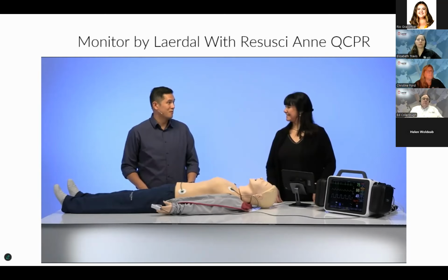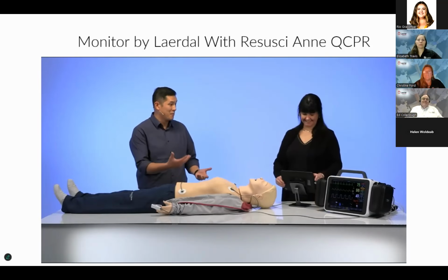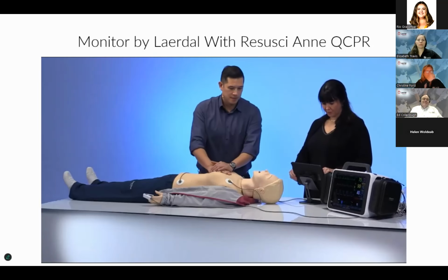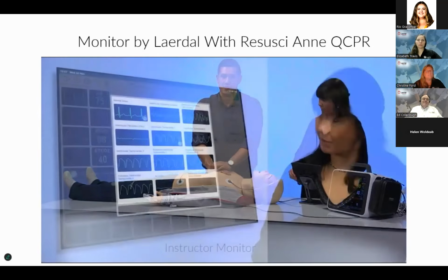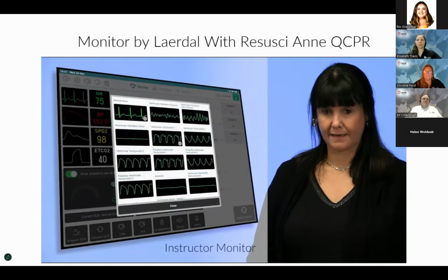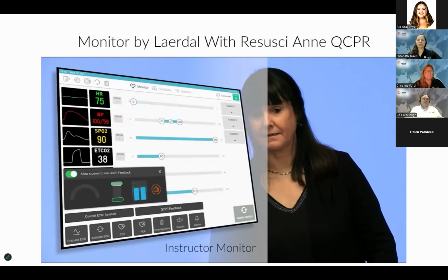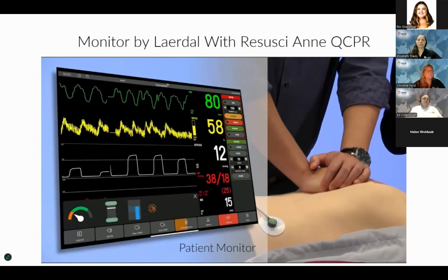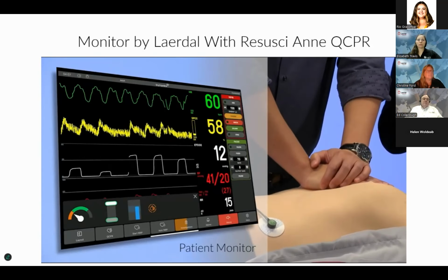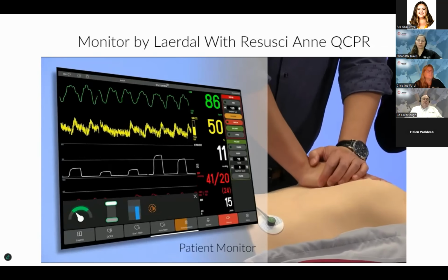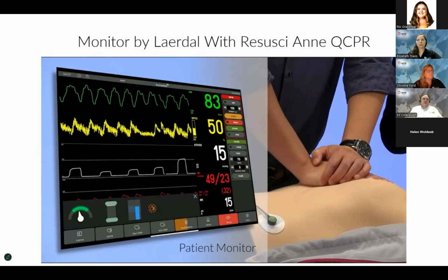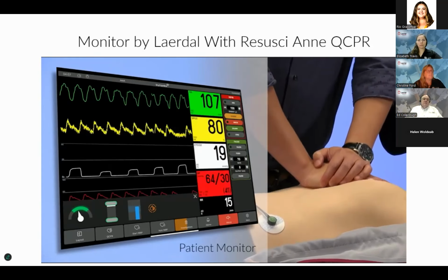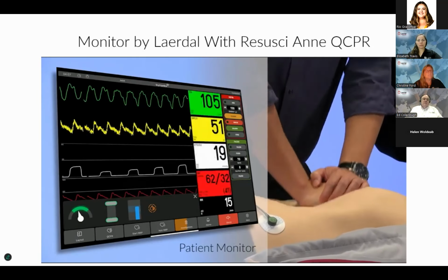Maybe, shall I give it a go? My CPR isn't the greatest, but maybe you can talk me through CPR and the whole process and how it works. Yeah, sure. I will choose a rhythm that requires CPR. Perfect. So you can go ahead and you will see the depth. The system is now asking to push a little bit deeper and a little bit faster. Yes, a little bit faster still. And also please note that the ECG curves and the SpO2 curves are also adapting to what you are doing.